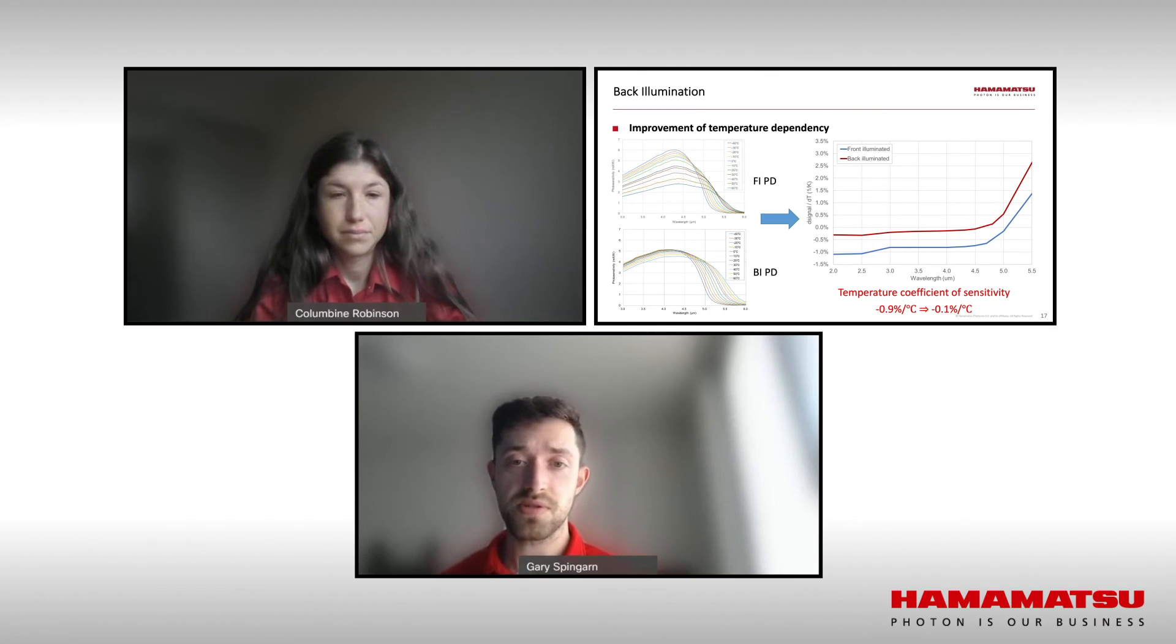Next comes back illumination. As we previously discussed and Columbine mentioned, photonic detectors have a noise floor, and then there is variance introduced through temperature changes. Through a proprietary structure, Hamamatsu now offers detectors with back illumination. This brings the temperature factor from 0.9% change in sensitivity per degree Celsius to 0.1%. This is truly an innovation and will definitely open doors to new applications, especially in portable instruments, especially because they require those small form factors and no cooling.